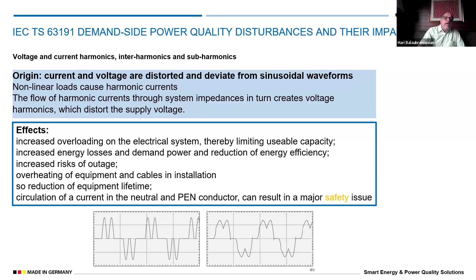Then we have the key parameters we need to consider for harmonics. THDV depends on the system impedance. THDV can be good or bad, because most supply systems are good in quality with a pure sine wave, and depending on the system impedance and on the current harmonics thrown into the system, the voltage THDV comes into effect.